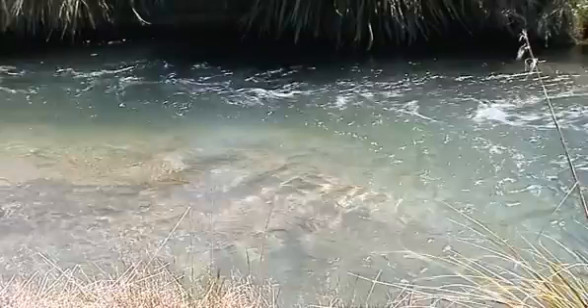We'll have a look at the discharge. What's been treated after it's been through the biofiltro bed — we just open this up out through the worm basket because Dallas told me he'd be rather upset if he thought any of them escaped. He said he's paid for them to work, so they should get back in there. As you can see, UV chambers — three sets of lights going across weirs. Because the total suspended solids are so low coming out of the bed and the liquid has a clarity to it, it lends itself to ultraviolet treatment. We run it over some rectangular weirs where we've got about eight mils of depth and UV lights above it, and we just polish off the remaining bacteria. As you can see, the discharge is completely different than what's been applied to the bed.